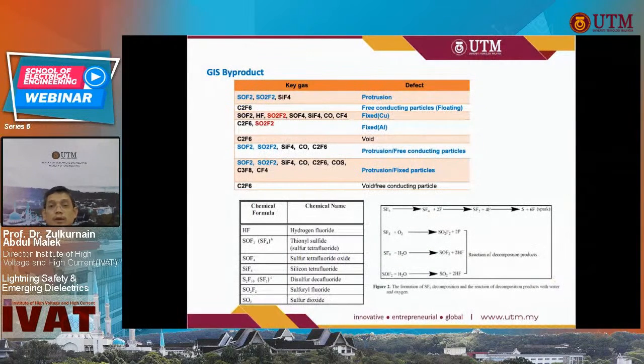Apart from solid, we also have what is called gaseous insulation. SF6 is used in many GIS, gas insulated switchgears. We have a 132 kV station with GIS switchgear on our campus here, and one condition monitoring that we need to do is continuous PD monitoring. And we can put sensors, but we can also do a very simple test by extracting byproduct gases. Sample the gas from the switchgear, send it to the lab and measure the byproducts.